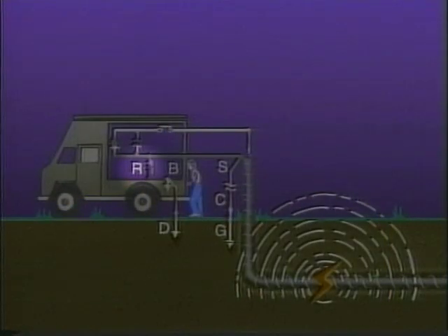Always use a shotgun to install it, and make certain that the ground is not connected to the faulted cable neutral. Do not use a redundant ground on thumpers that have the resistor installed, or you will short the resistor out of the circuit, and this will defeat the purpose of the resistor.